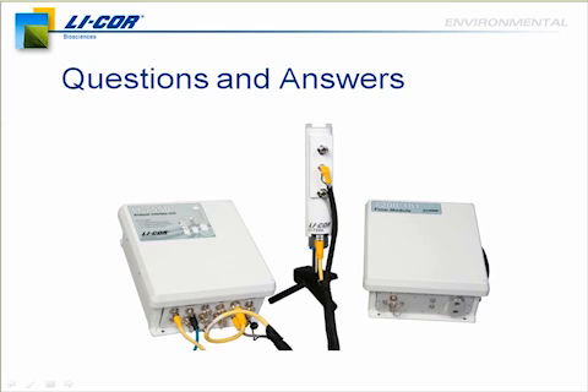And so the 7200 is really a new kind of instrument that takes an open path analyzer and encloses it to give us what we feel is really the best opportunity to make remote flux measurements. And that's why we've branded this an enclosed analyzer, because it's not a traditional open path and it's not a traditional closed path. It's really something new and different.